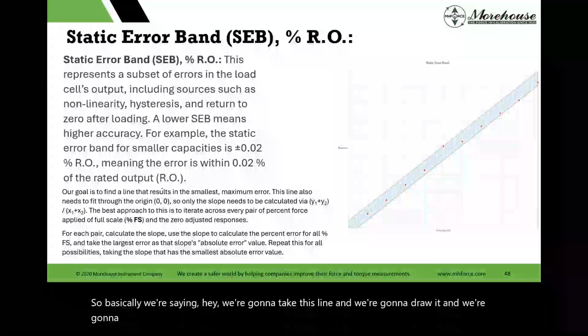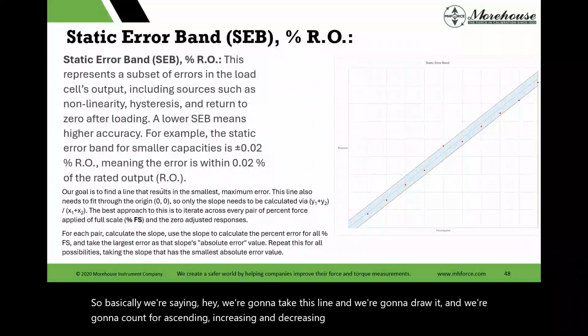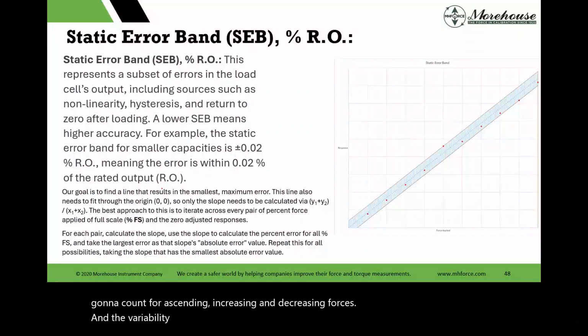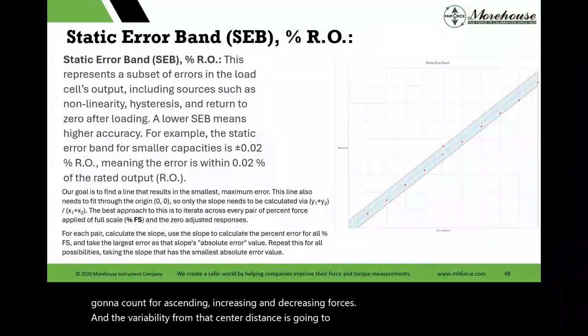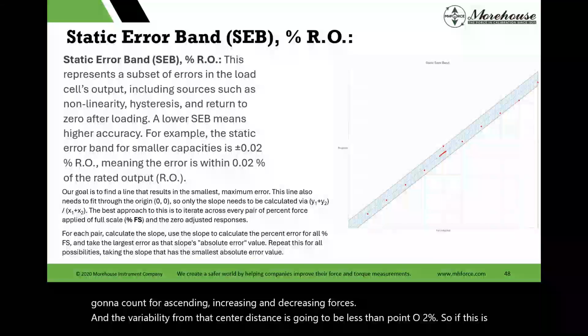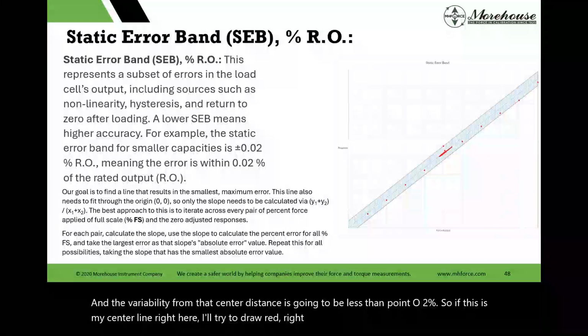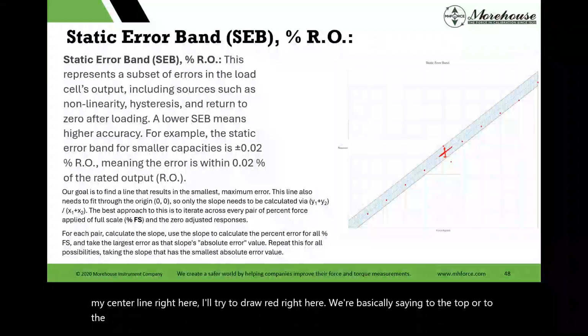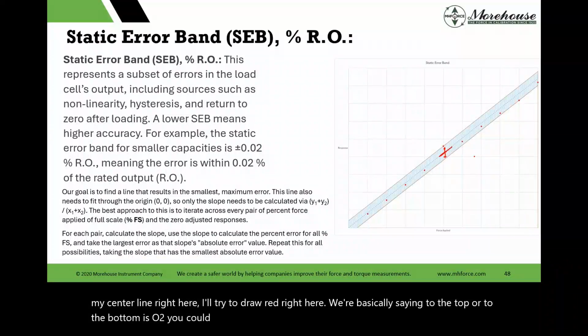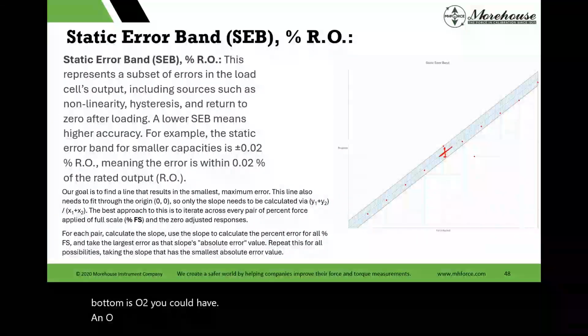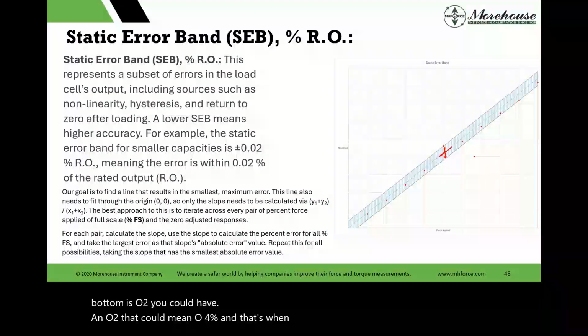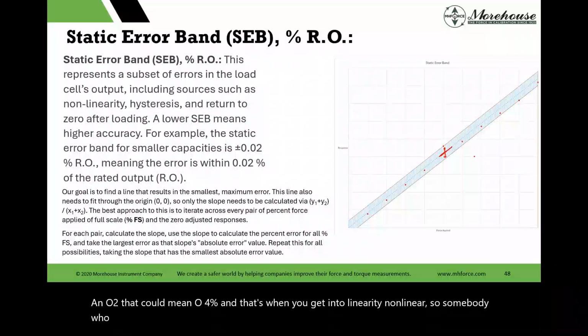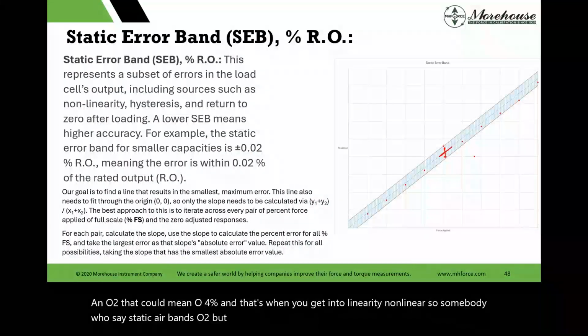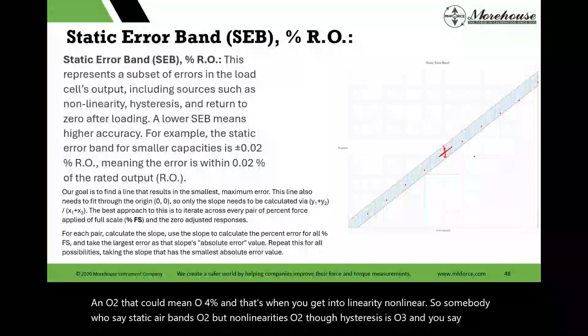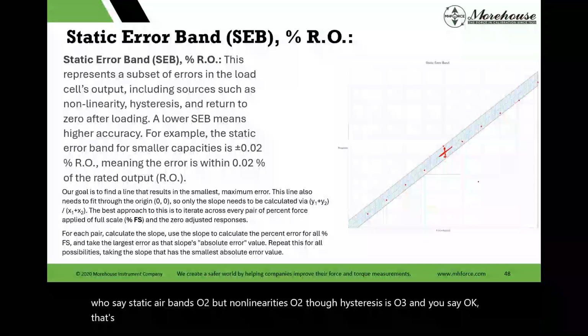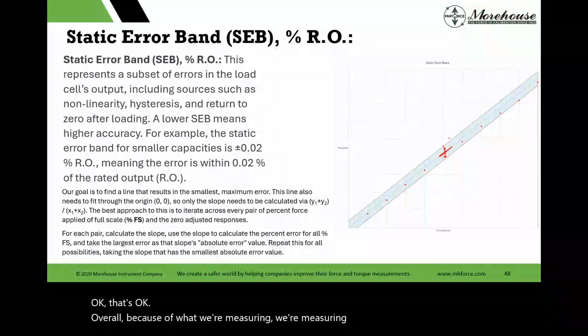So basically we're saying, hey, we're going to take this line and we're going to draw it, and we're going to account for ascending, increasing, and decreasing forces, and the variability from that center distance is going to be less than 0.02%. So if this is my center line right here, I'll try to draw it red right here, we're basically saying to the top or to the bottom is 0.02. You could have an 0.02, that could mean 0.04%, and that's when you get into linearity, nonlinear. So somebody would say, well, static error band's 0.02, but nonlinearity is 0.2, though hysteresis is 0.3, and you say, okay, that's okay overall because of what we're measuring. We're measuring and how we're plotting it.